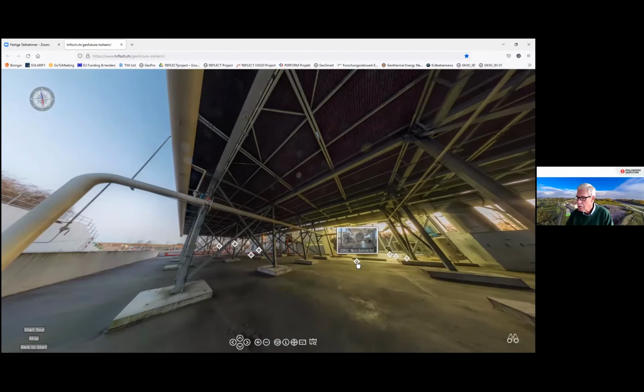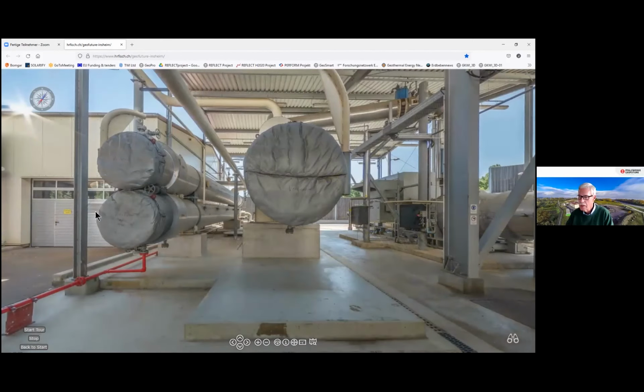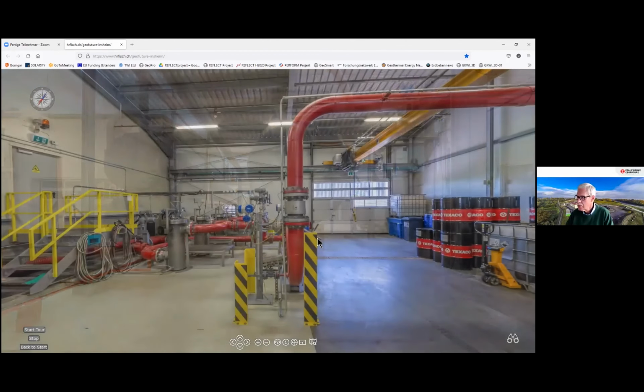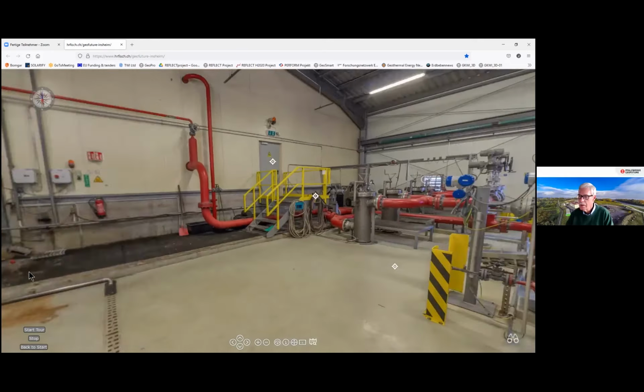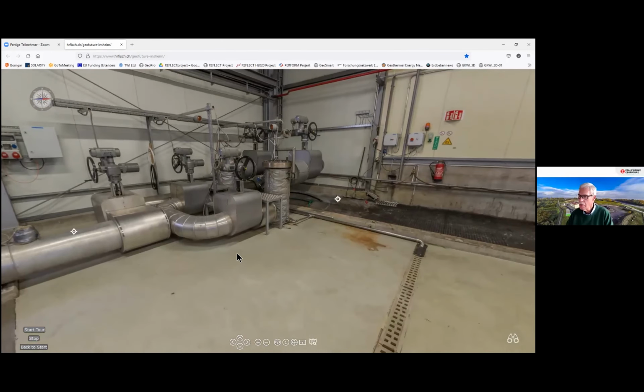But what is more important for us is to have a look back into our brine treatment facility, because due to our very high mineralization, we have to take care that we have a proper operation of our brine. So the hot brine is coming by this pipe directly from our production well. Then we have a filter section with 2 parallel filters with baskets with a mesh of 150 microns. These filters are permanently in operation, but have to be maintained only after a restart, after a longer maintenance shutdown. Then we will have mobilization of fines, but as well scalings, which occur by restarting the pump.